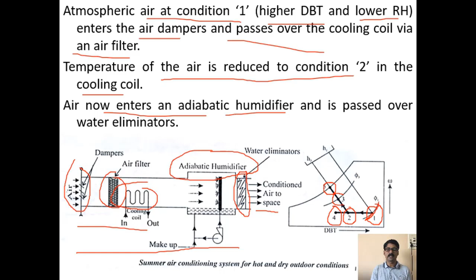Now air enters the adiabatic humidifier, wherein it is humidified. Adiabatic humidification means water is sprayed, and it gets evaporated and induced into the incoming air, thereby its temperature reduces. Here you can see 2 to 5 is the adiabatic humidification. If 100% humidification is there, then it will reach the saturation point at 5, but 100% humidification is not possible, so it will end up at state 3.